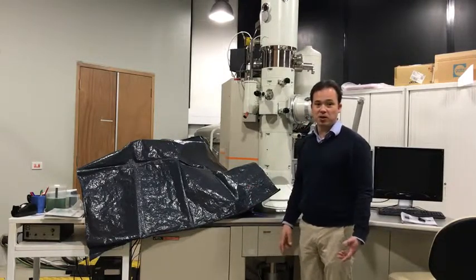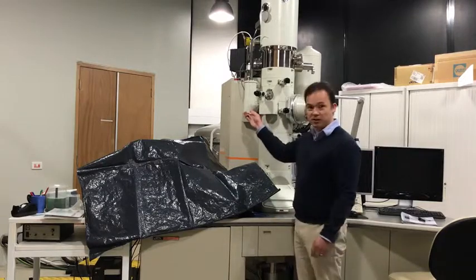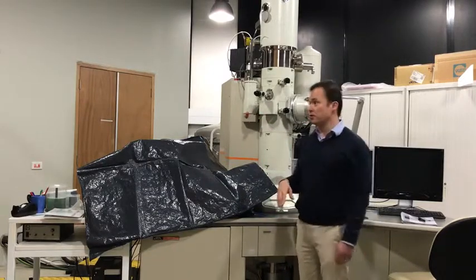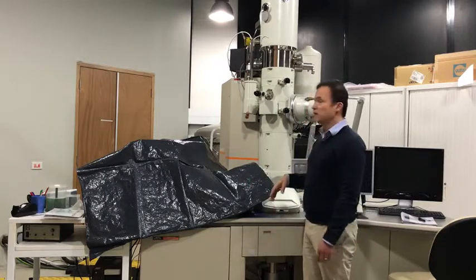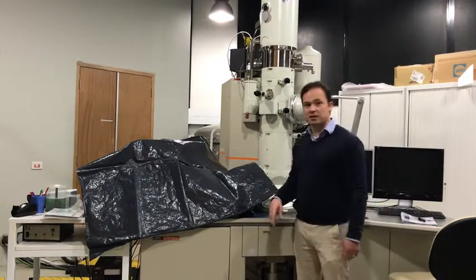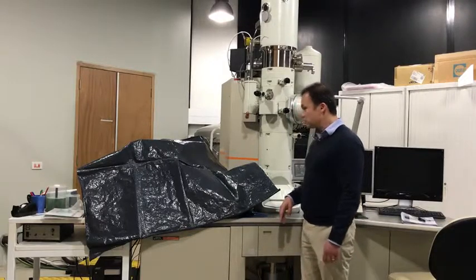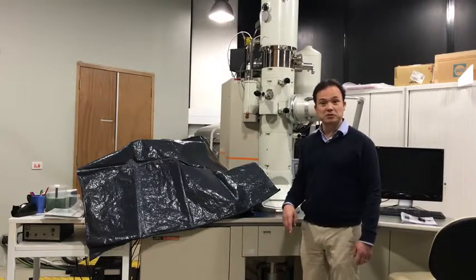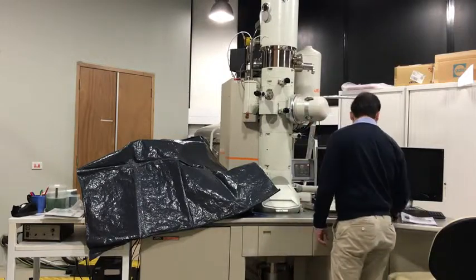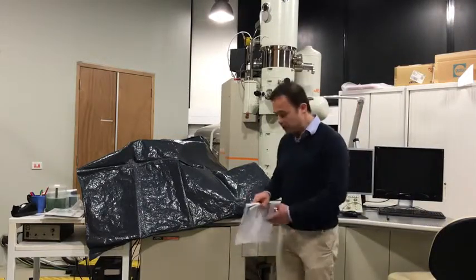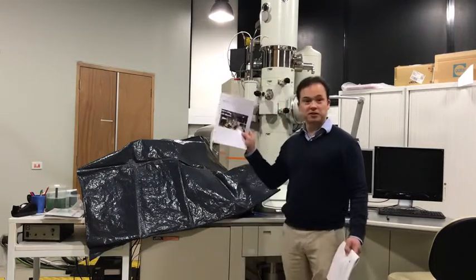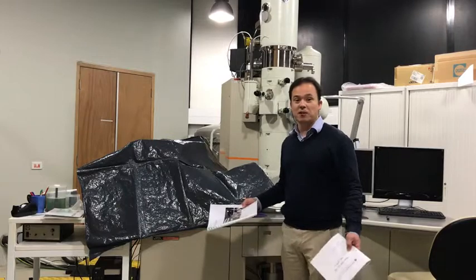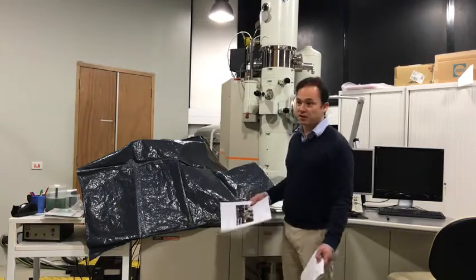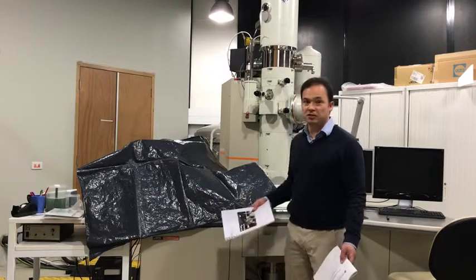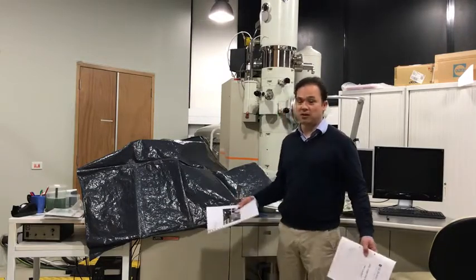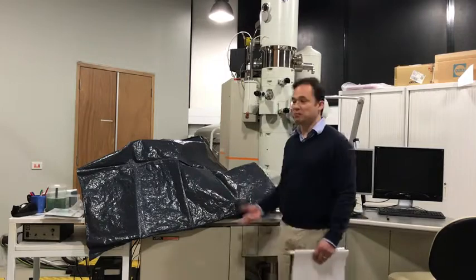Now, startup takes quite a while. We have to put a specimen in, we have to cool the cold finger down, we've got to start detectors, we've got to check that the water flows are correct, check the vacuum is correct. There's quite a lot to do. So I'm going to very quickly lead you through that process. In order to do that, it's a bit like flying a plane. We have a checklist, right? So every pilot, when they fly a plane, they go through a pre-flight checklist, and those checklists are an industry standard so that the pilot doesn't forget something and crash the plane. It doesn't matter how much experience the pilot's got.